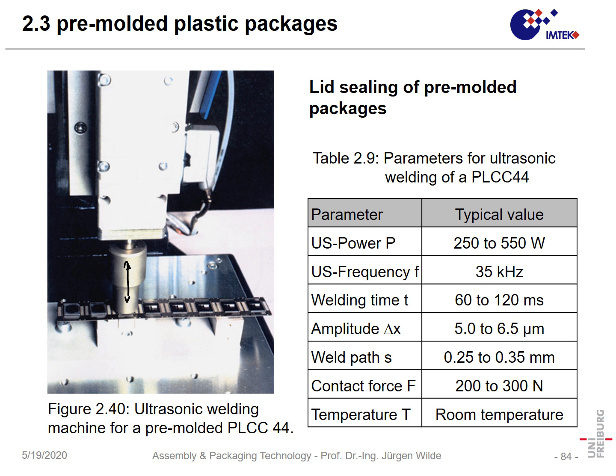We had an ultrasonic welding machine. For that machine, you put on the lid. You have a tool. That tool is moved by ultrasound. The ultrasound can have a power of 250 to 550 watt. The typical frequency is 35 kilohertz. You will not be able to hear it, but maybe you feel it because it's a very high power. And within less than 1 second, this action of the ultrasound will lead to a local melting of the package. The amplitude also is very low. It's just 5 micrometers of vibration. And with that vibration, the whole package is deformed, for instance, by 0.3 millimeters.